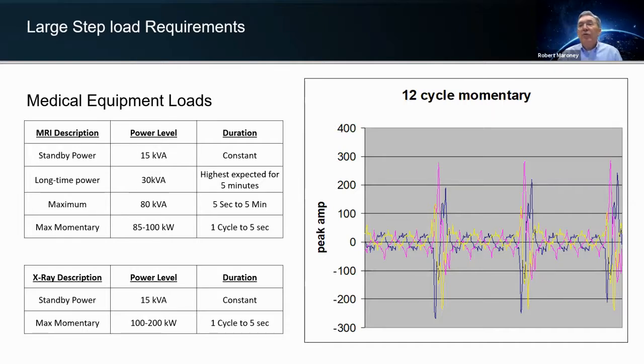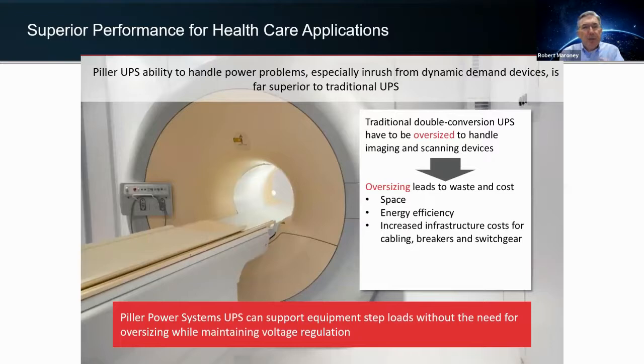You don't want to be going to bypass or your energy storage on that. You want to be able to support those very, very fast spikes without having to make those transitions. You don't want to be going to bypass and having your imaging gear on utility during bypass because the UPS had a limitation on its ability to cover these kinds of loads. Imaging and MRI equipment, so you'll see our stuff there a lot.